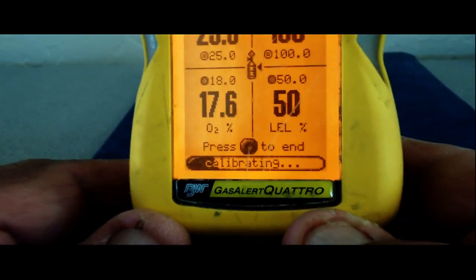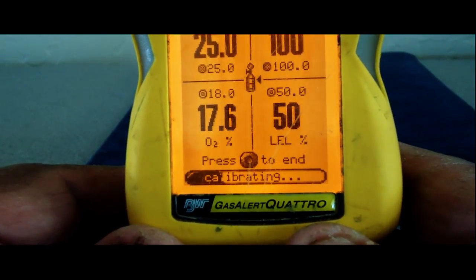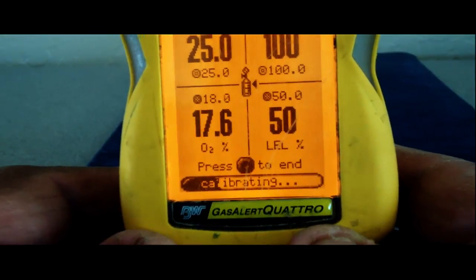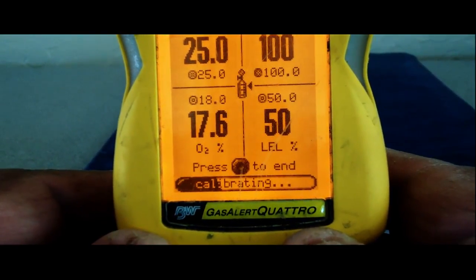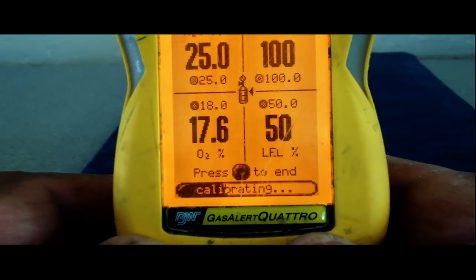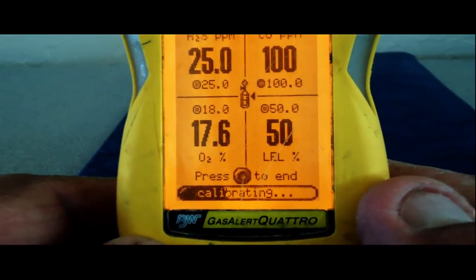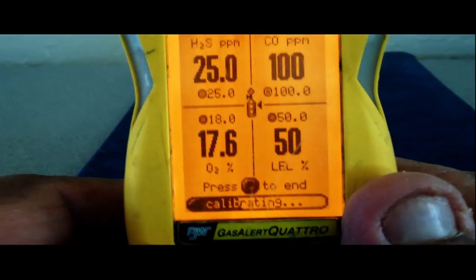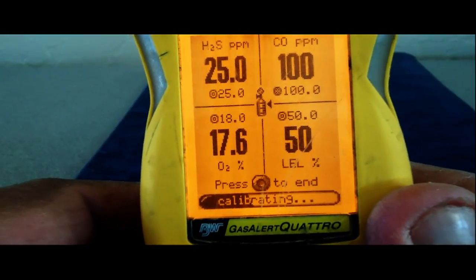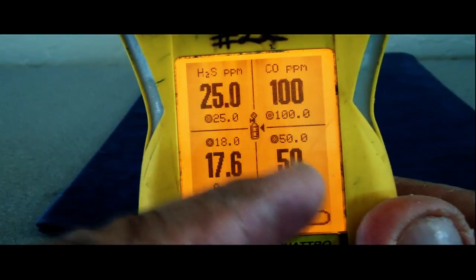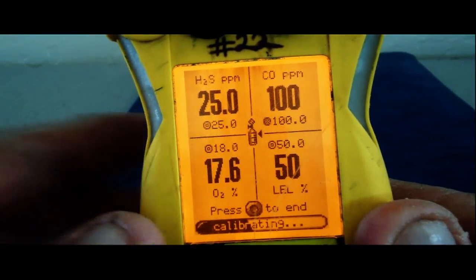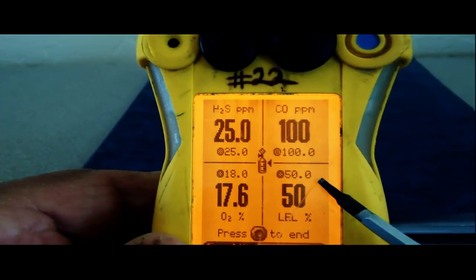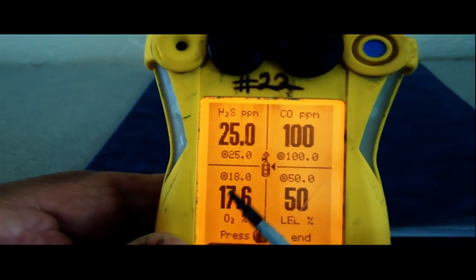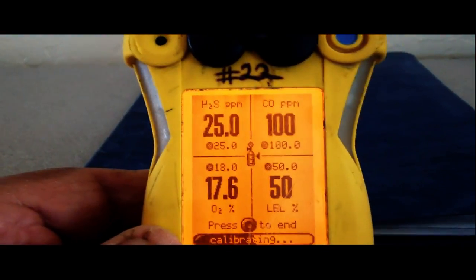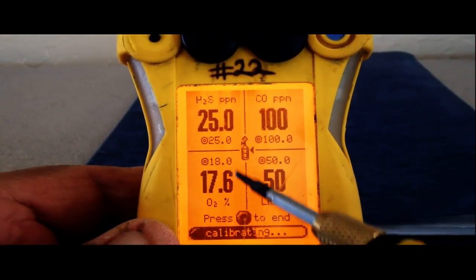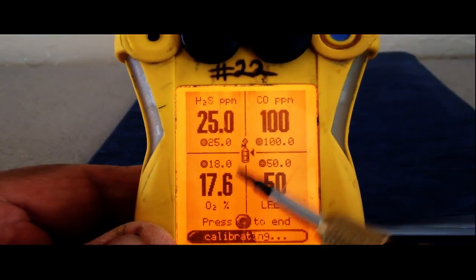That's awesome. Now you'll notice on the bottom of the screen there's a little black bar. As this machine calibrates, the bar will move and tell you you're getting closer and closer to a calibration being complete. If you're in the calibration phase and you cannot reach the values for each, you'll see it says it wants 25, it wants 100, LEL is 50, and O2 is 18. The 18%, we're at 17.6, but that's okay. It's telling me that I'm getting a reading on O2, so I'm comfortable with that.